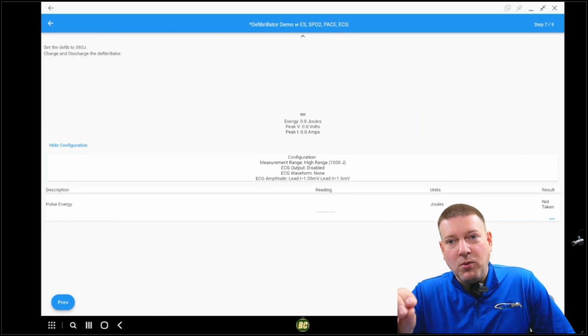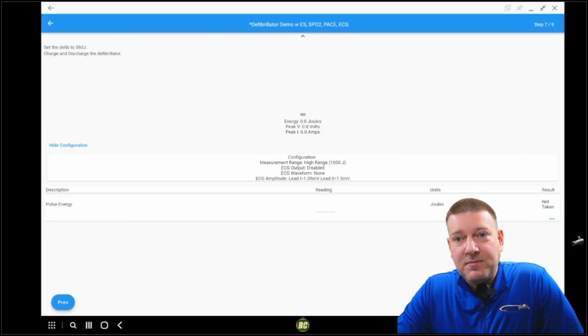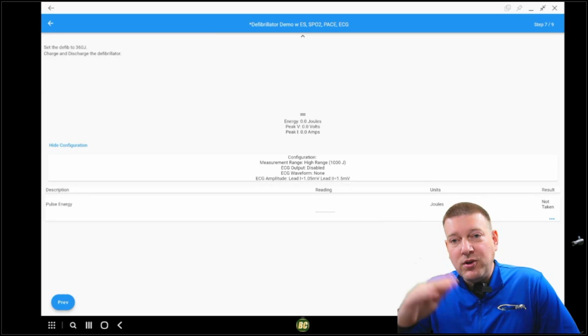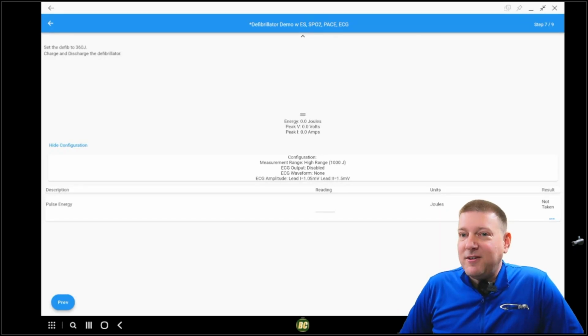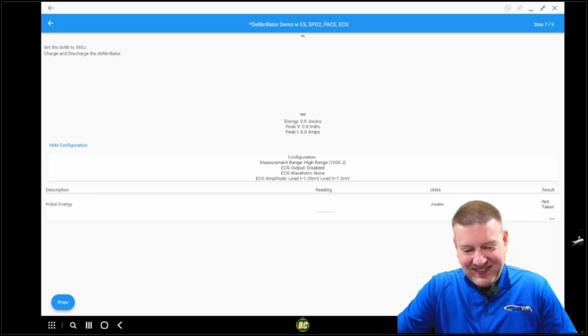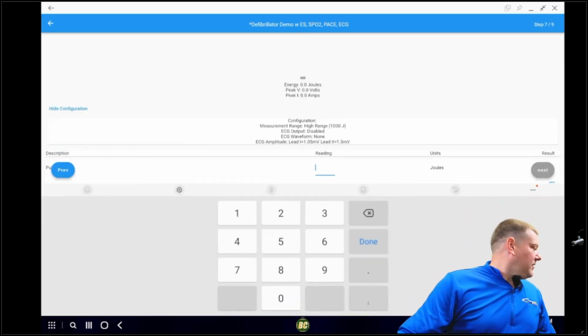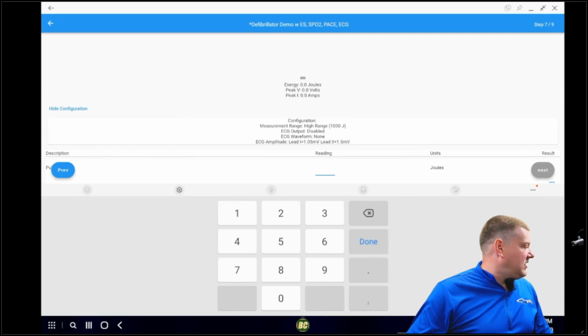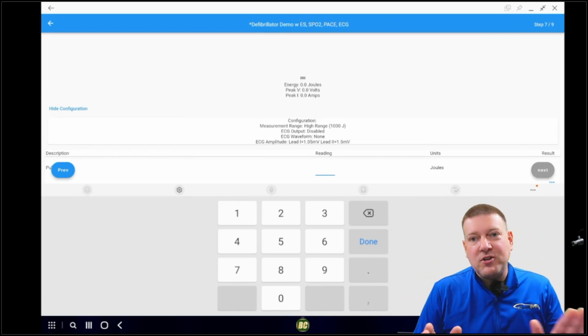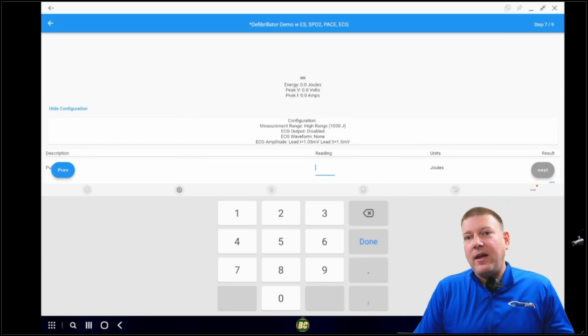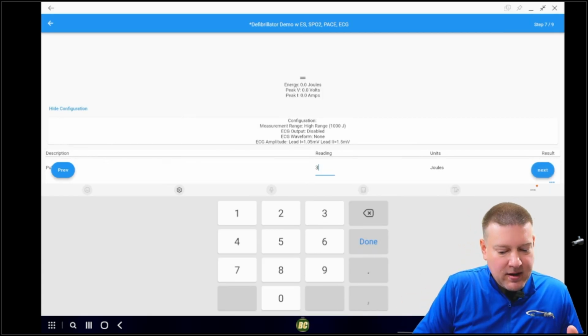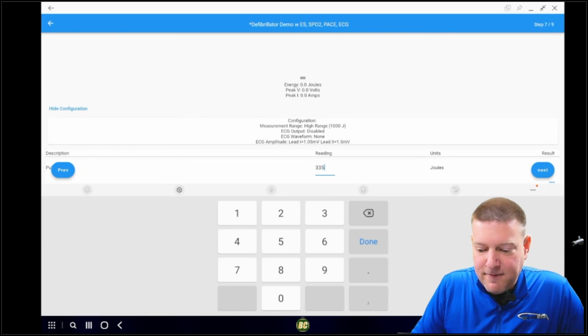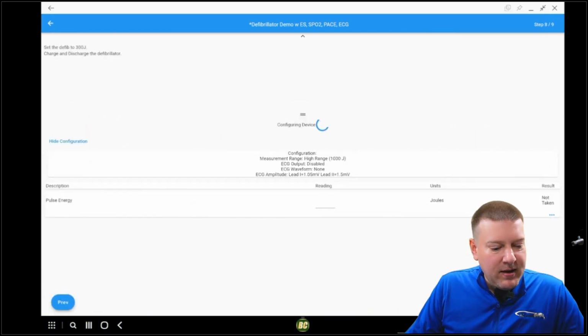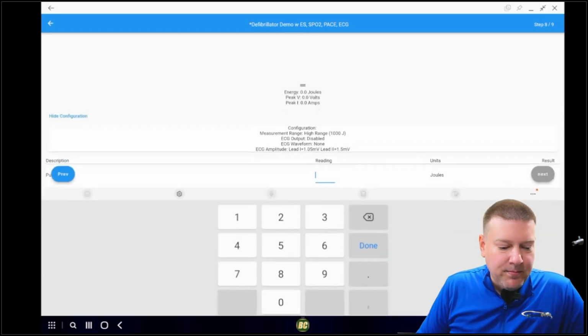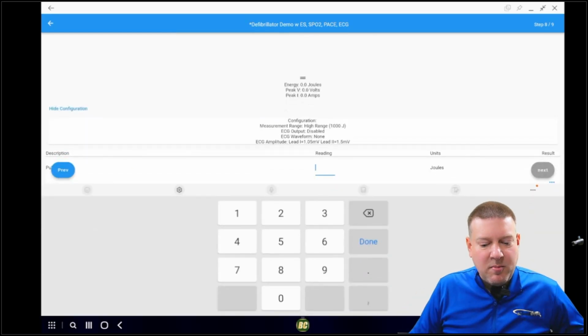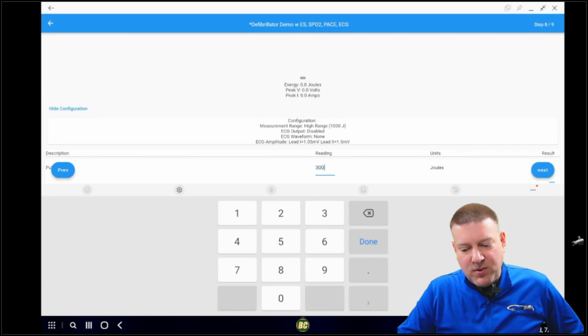It gives me pass conditions, and then it proceeds to the next part automatically. So what we're doing is we're going to complete all the steps on a page, and then when the icon turns blue, you can proceed to the next. If it doesn't go blue, there's something left to do. All right. Pulse energy. This is where I would charge the defibrillator, discharge it. It will automatically capture any sort of input whatsoever, and it's going to put it right here. So on this particular one, let's say 335. And then I created one more step, which I have to go in and write the description a little bit better. And this one here, I put for 300 joules.